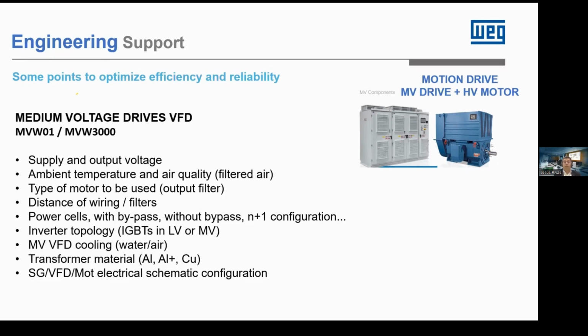The ambient temperature where the drives have to be located is important to calculate the efficiency. The air must be filtered. The location must always be taken into account. We also look at the type of motor that the drive is going to feed, because you have to know what insulation it has. The motor has to be prepared to be fed by a VFD. We consider the distance of the wiring from the inverter to the motor, although in water plants this is not usually a problem. They are normally quite close, less than 300 meters, so there is no need for filters, although it could be the case.